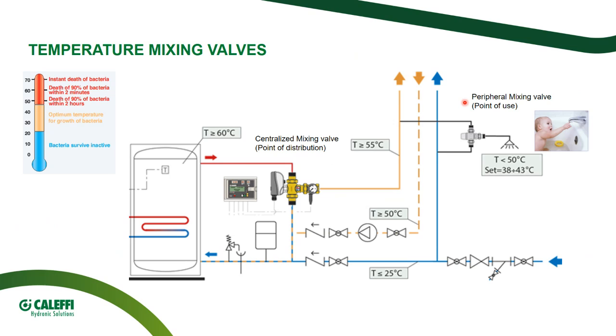So we can easily identify 3 areas: the storage, where the temperature is kept at a very high value. We are speaking about minimum 60 Celsius degrees. This is for the safety. This is for the safety versus Legionella. I think everybody knows already what Legionella is. The Legionella is a bacteria living in the water, naturally present there.